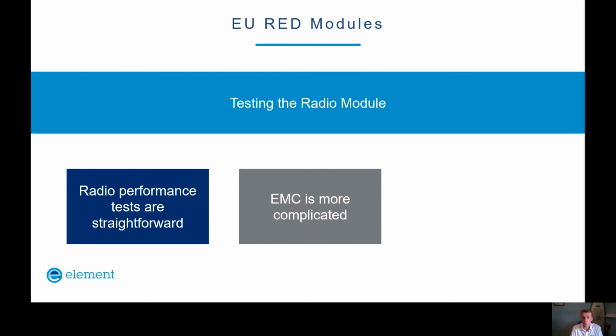EMC is a little bit more complicated. The radiated immunity testing, for example, would typically need to be done with an antenna connected, so a typical antenna would be used. For ESD, you're not going to want to hit a delicate little module with an ESD gun, so typically people will do the vertical coupling plane and horizontal coupling plane around the module. But a lot of the other EMC tests simply aren't performed if the manufacturer states that the test jig has short cables, for example.